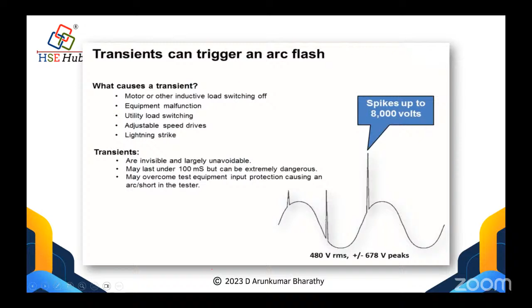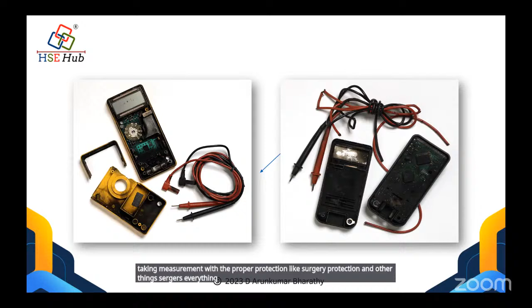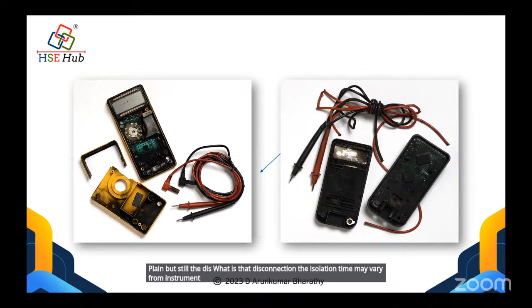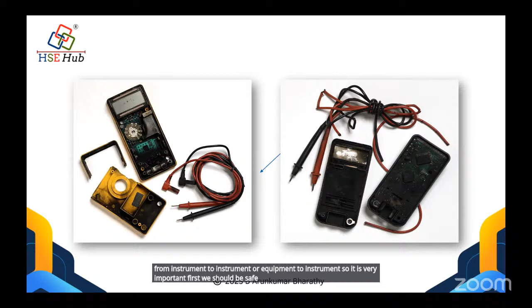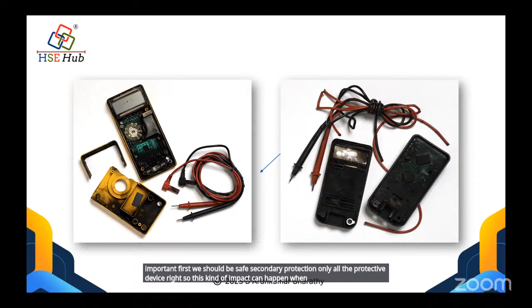See what happens? Within 10 microseconds it can happen, and by this time it will burn the meter, and it may also electrocute the person, right? This kind of impact can happen. So selecting and using the instrument are very, very important, and so is understanding the transient. If I am taking a measurement with proper protection like surge protection, fine. But still, the isolation time may vary from instrument to instrument or equipment to equipment. So it is very important that first we should be safe. Secondary protection only, all the protective devices, right? This kind of impact can happen when it is not understood in a proper way, especially the transient, surge, whatever it is.